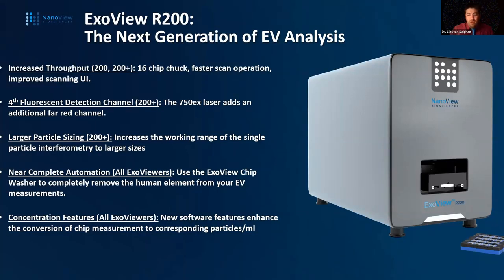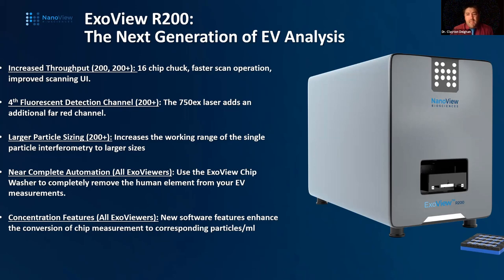The R200 is the next generation of EV analysis. There are two models: the R200 and the R200+. Both come with increased throughput, centered around a 16-chip chuck — versus nine chips in the R100, you can now read 16 chips in one scan. The stage design offers about 25% faster scan times and an improved scanning UI. The stage automatically detects the presence of the chuck: when you set it on, it will automatically take the chuck inside, begin its scan, and put it back out — useful for remote operations.